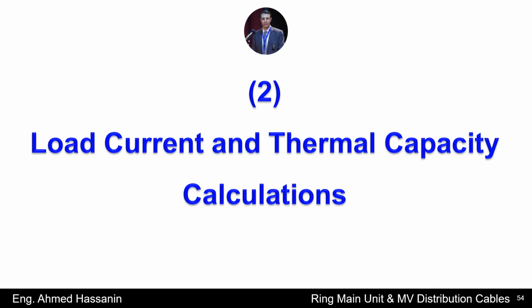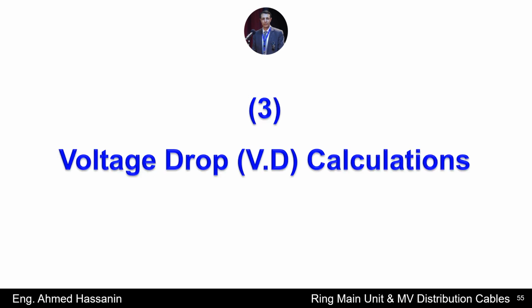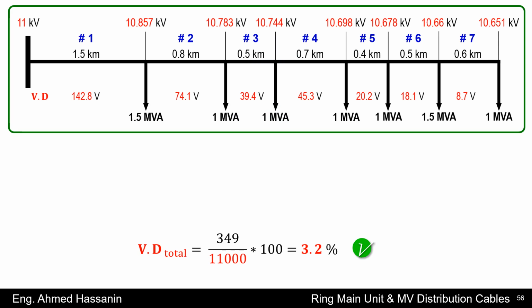In the second step of the second method, I will explain how to calculate the load current and thermal current for the medium voltage cables of the ring system. In the last step of the second method, I will calculate the voltage drop. As we see in the figure, in detail and step by step, I will calculate the individual voltage drop for each part of the medium voltage cables of the ring system and the total voltage drop for the ring system.